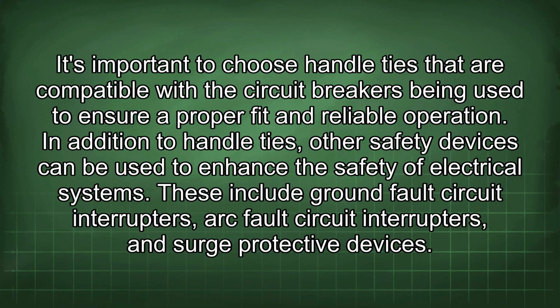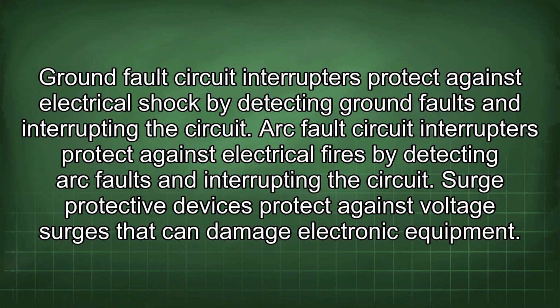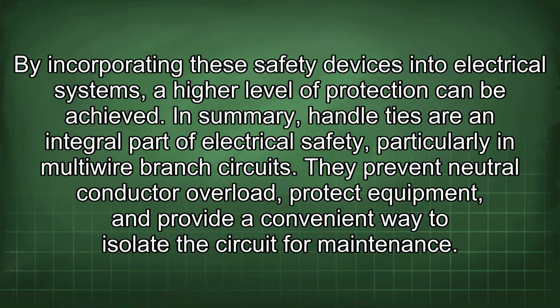In addition to handle ties, other safety devices can be used to enhance the safety of electrical systems. These include ground fault circuit interrupters, arc fault circuit interrupters, and surge protective devices. Ground fault circuit interrupters protect against electrical shock by detecting ground faults and interrupting the circuit. Arc fault circuit interrupters protect against electrical fires by detecting arc faults and interrupting the circuit. Surge protective devices protect against voltage surges that can damage electronic equipment. By incorporating these safety devices into electrical systems, a higher level of protection can be achieved.